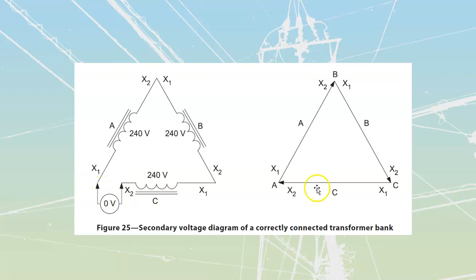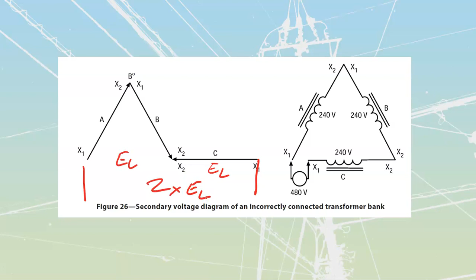The reason for that: if we take a look at those transformer coils we stepped through - A, B, C - there should technically be 0 because it comes back to the same point as far as our phasors are concerned. But if I had one of my windings flipped, in this case the C winding flipped, what would actually happen is this thing gets extended out further. So if I measure from this point to this point, and if this is E line and this is E line, that means I'll be measuring double my line value of voltage.